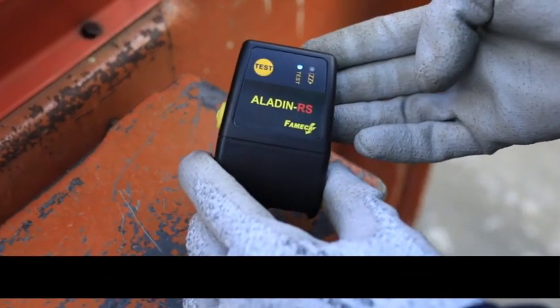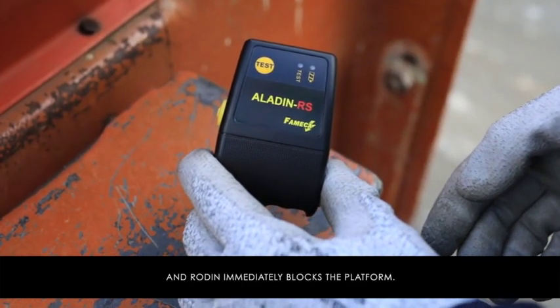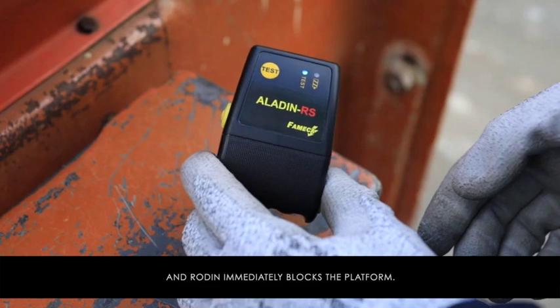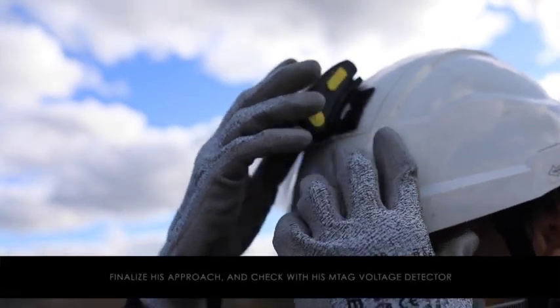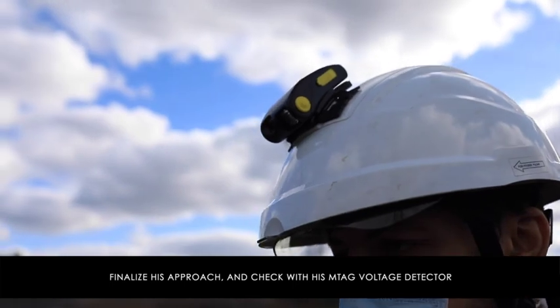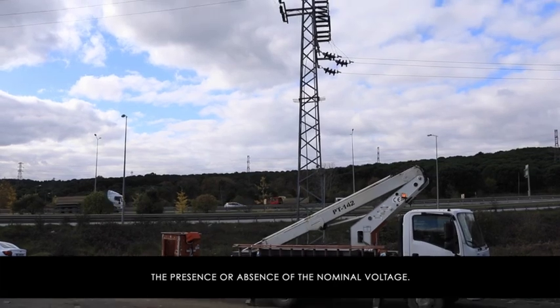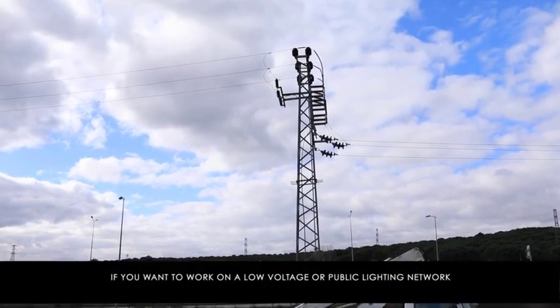The system constantly monitors the presence of the operator in the platform. If this is not the case, the hydraulic circuit is rendered inoperative. Aladine warns of the danger if an unexpected voltage is present in the conductors, and Rodin immediately blocks the platform. After analyzing the situation, the operator can acknowledge and finalize the approach.